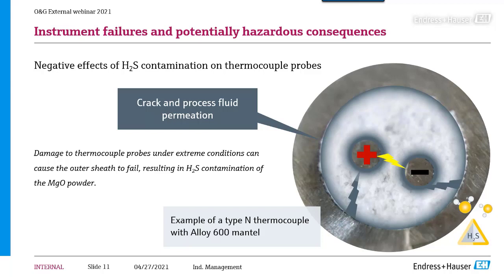When that happens, what appears is this yellow flash, and this yellow flash is everything not positive, normally a short circuit in the thermocouple. That's extremely dangerous because you don't know where it happens. It can happen at the tip of the thermocouple, in which case you're very lucky, or in most cases it happens along the thermocouple, maybe at the beginning, the middle, or close to the end.